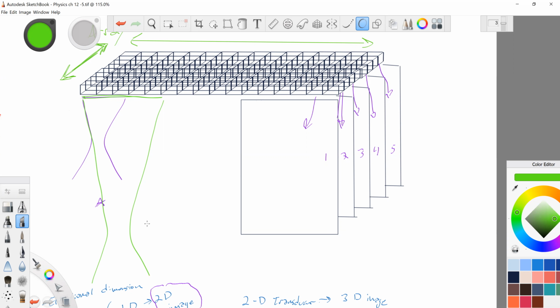So a dynamic aperture doesn't have to be 10 elements every pulse. It could be 8 elements for pulse 1, 10 elements for pulse 2, and the focus 3 could have 12 elements being used. It's just adding to the pie. It's not absolutely necessary. You could not use dynamic aperture and get the same effect simply by phasing, simply by timing your outside to inside elements. So that's dynamic aperture on the way out. That's the one I almost forgot to tell you guys about.